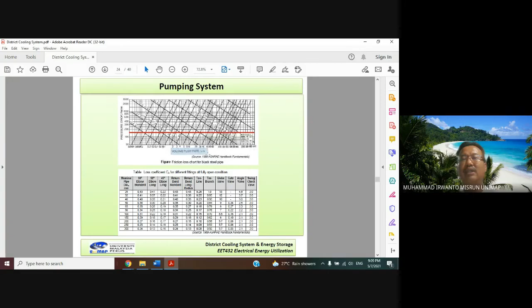and since the length of the pipe is given in 150 meters, we have to convert the flow rate into liters per second. Remember, 1 cubic meter equals 1000 liters. So 0.139 multiplied by 1000 liters, we obtain the water flow Q as 139 liters per second.